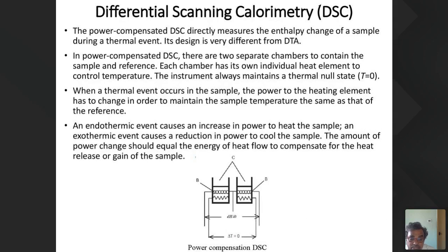Here, power compensated DSC is most widely used. The sample is kept in a separate furnace, unlike what you can see in DTA. When a thermal event occurs in the sample, the power to the heating element has to change in order to maintain the sample temperature the same as that of the reference.